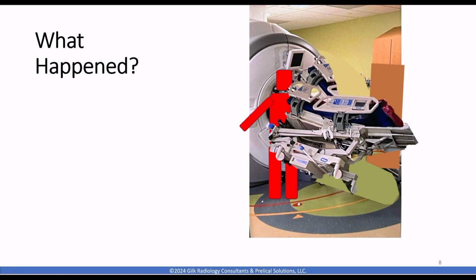From this accident, if you look at the image of where the nurse was, how do you get the nurse out from that position? Now, I said the magnetic field of an MRI is 24/7, 365. Generally speaking, that's true. There is a button you can push that's called a quench button that de-energizes the MRI's magnetic field. It's not without its own risks associated with it. But the rad tech felt as though, or believed that she needed to get external approval to hit that big red button. And so instead, she goes to the nurse who's pinned between the ICU bed and the MRI scanner, and I choose my words carefully, grabs her by the arm and rips her out from between the ICU bed and the MRI scanner.